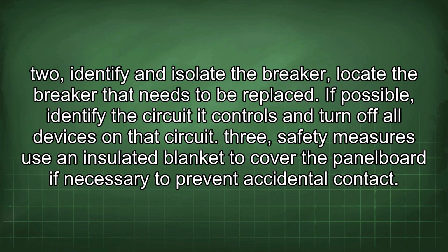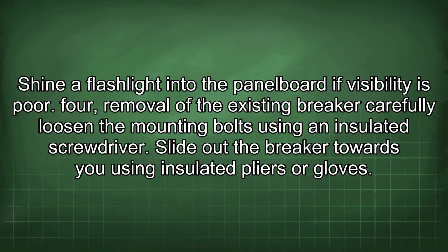2. Identify and isolate the breaker. Locate the breaker that needs to be replaced. If possible, identify the circuit it controls and turn off all devices on that circuit. 3. Safety measures: use an insulated blanket to cover the panel board if necessary to prevent accidental contact. Shine a flashlight into the panel board if visibility is poor.